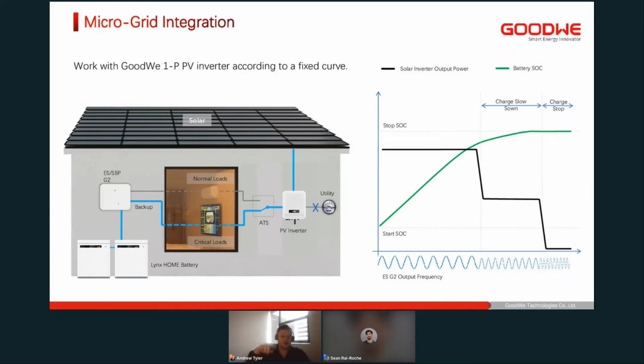And you'll notice that when you've got a very open frequency, such as starting from the left, the inverter will be charging at full power. And then when you are seeing the battery level reach 50%, for example, the frequency actually starts to go up to maybe 52.5 hertz or 62.5 hertz, depending on the market, and that will then slow down the charging. And once that frequency goes to, for example, 55 or 65 hertz, then the grid side inverter will stop producing power completely. So it's quite an intelligent way of being able to control the grid side inverter without necessarily having a complete GoodWe solution.